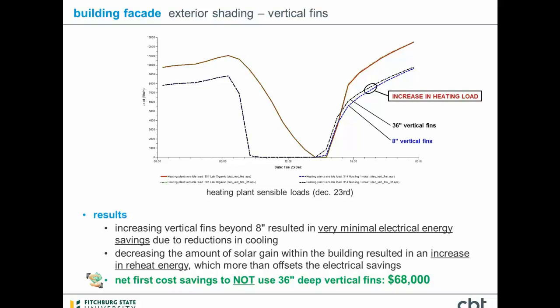Partly, I think it was due to the fact that the horizontal shades were allowing in the winter sun. So this is actually a bit of a trick slide. We're not looking at cooling plant in this particular slide, but the heating plant. And I think one of the key points to take away there is, as you may be looking to isolate one variable, like looking at a reduced cooling load, you need to make sure that there isn't an unintended effect at the same time. So we ran cooling simulations.